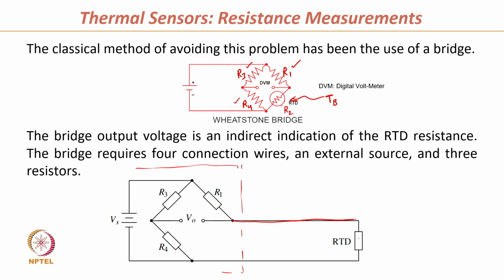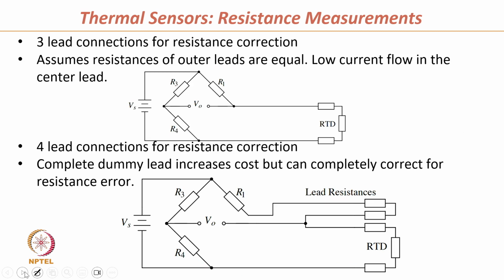Only this RTD is taken away using these lead wires, and this area is exposed to the temperature which is TB, which is some higher temperature. Now, because of these extra lead wires, we still have some resistances of these lead wires. So, this is the extra lead wires which we have here, which causes the error in the measurement. So, what we do, we take this kind of assembly where we have this RTD, these are the lead wires, and we take measurement at this point only, and we connect extra lead wire here on the other side of this measurement to compensate for this extra lead wire.